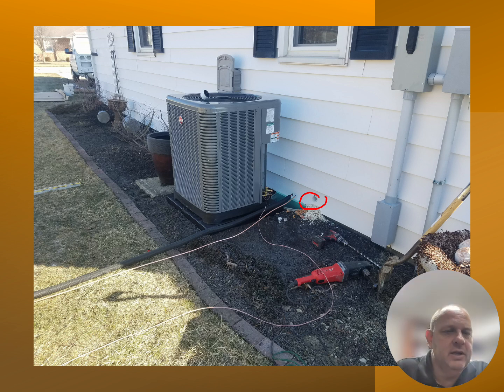Now, as far as the pressure testing and as far as the microns that we need to drop this unit down to, you're going to have to read the manuals on these particular units because they're talking about pulling vacuums and breaking them and pulling them and breaking them. They're talking about triple vacuum on these units. So you're going to have to really, really pay attention to the manual and what these manufacturers are wanting from you, the installer, for this particular unit.